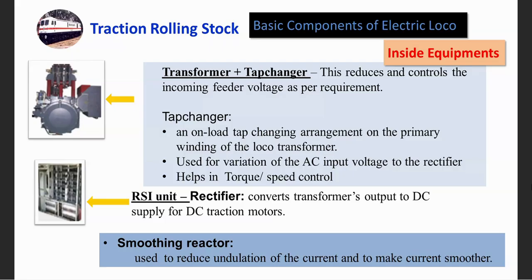We use a smoothing reactor, and its function is to remove the undulation of the current and make it as smooth as possible, as close to DC current as possible. So we have the transformer, tap changer, rectifier, and smoothing inductor.